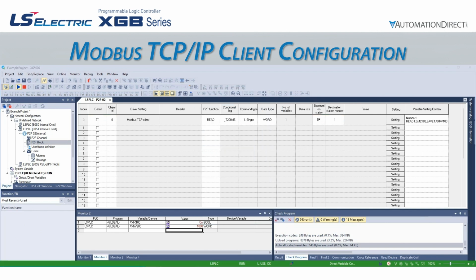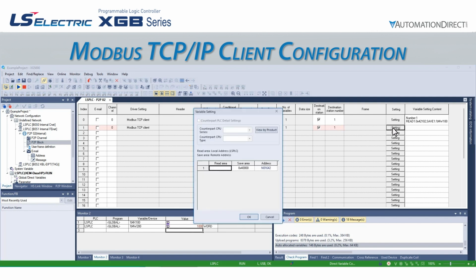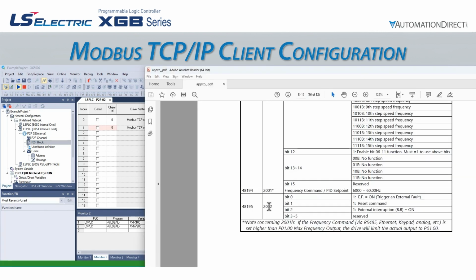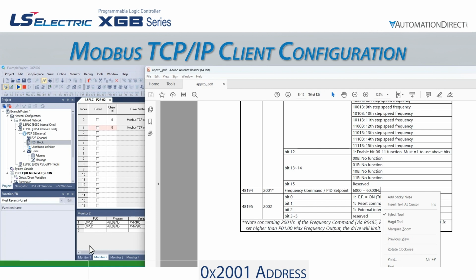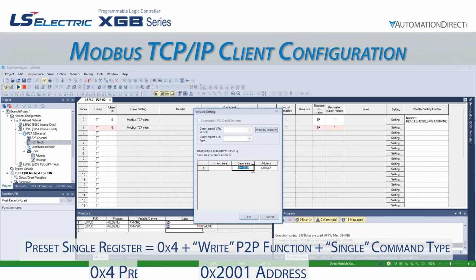We will do the same for the write message to control the drive preset speed. We use index 1, set it to channel 0, make it a P2P write function with an update rate of 200 milliseconds, a command type of single, data type of Word. For our variable content settings, we look in the drive manual and see that the address for controlling the drive frequency is 0x2001. So we will use 0x42001, and we will write the data from %MW101.